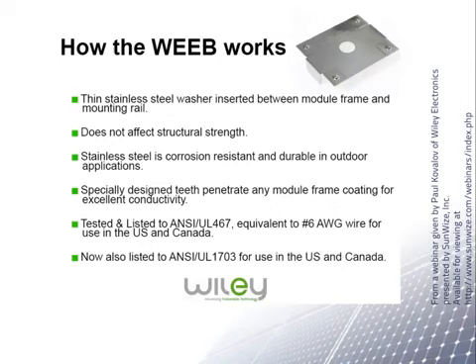It has teeth on the top and bottom so that when the module frame is bolted securely to the rail, the teeth dig into both the frame and the rail. The teeth dig beyond the non-conducting surfaces on the top and bottom and make an electrical contact with the conductive metal beyond the surface. When WEEB connectors came out, the manufacturers claimed that the ground connections were as good as the traditional ones using copper wire, but not everyone was convinced.